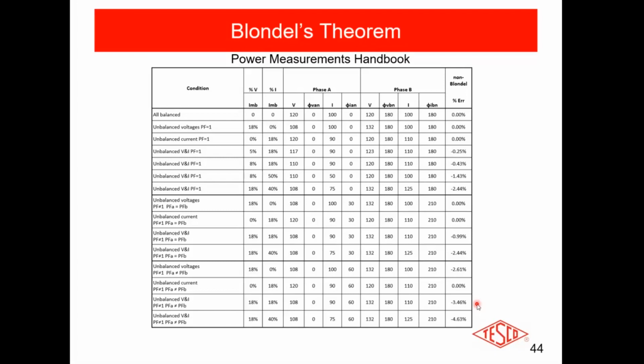Is it 0.7? No, it's not that bad, but it's not 1, which means that if I have an unbalanced voltage, which I typically do, and I've got a slightly unbalanced load, which I typically do, and my power factor is not 1, the odds are that my 2S meter is no longer giving me accurate information. How far in, how off is it? Is it 0.5%, 0.25%, 1%? And the answer is yes. It could be all of those things. But you're losing a certain amount, and it's getting worse year after year after year the longer we use our 2S meters.